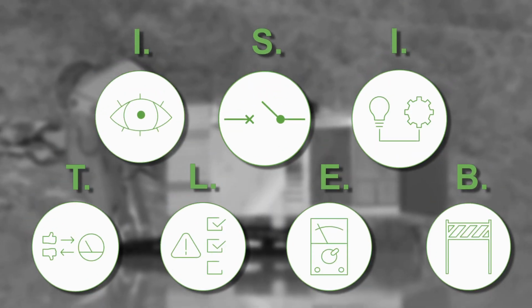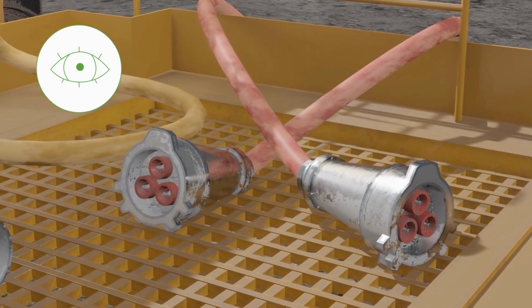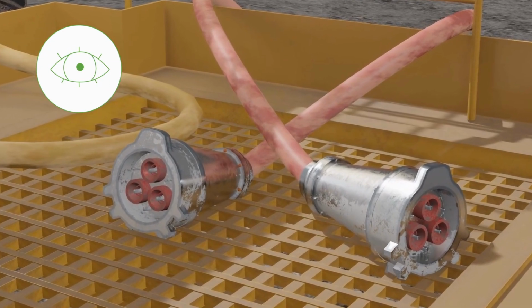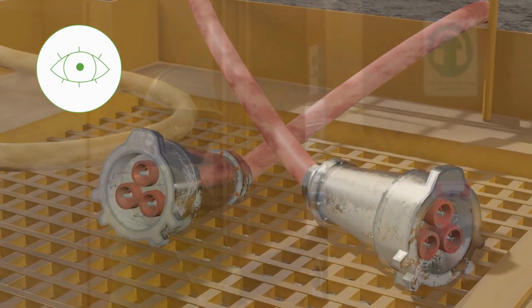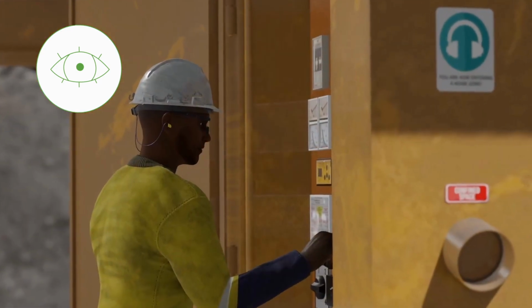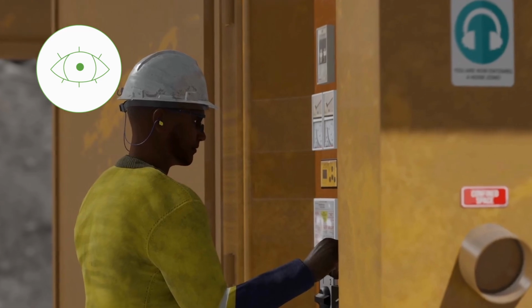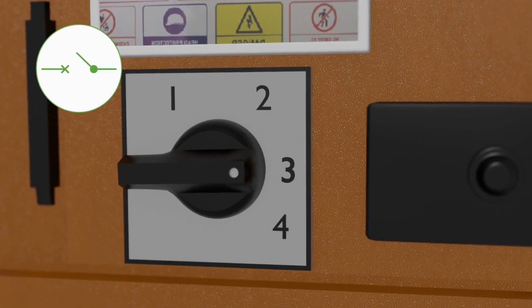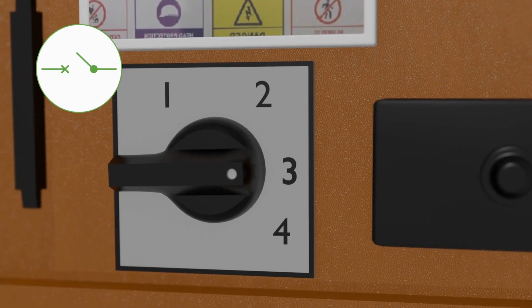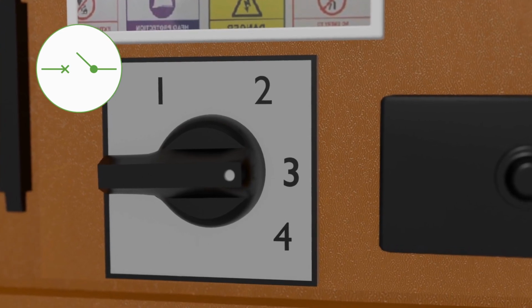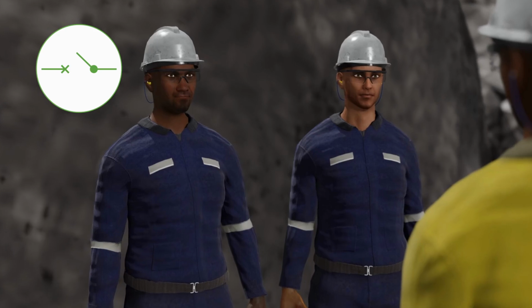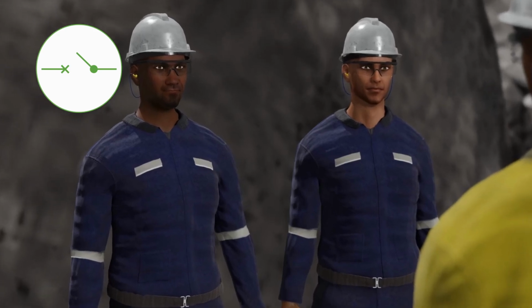To prevent similar incidents, it is essential to adhere to the I-SIT-LEB process. Identify: inspect all equipment, energy sources, isolation points, and hazards. This step would have revealed the live ring feed and avoided incorrect assumptions. Switch: deactivate all energy sources using approved methods like opening circuit breakers. Ensure this step is documented and verified by the entire team.